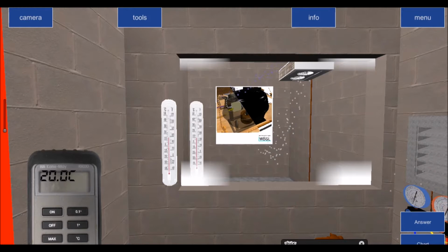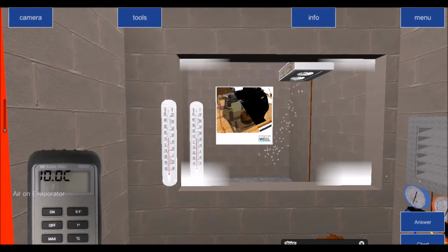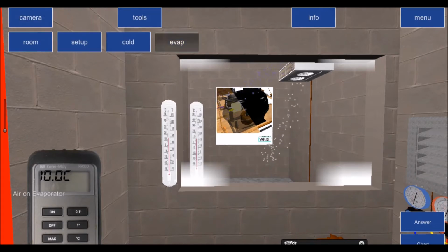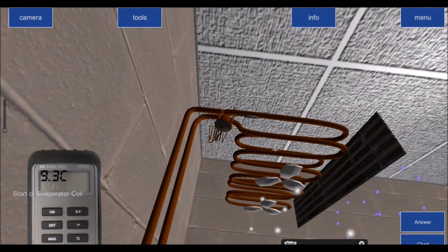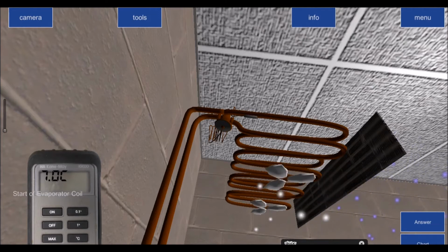Now, sticking with this particular job, we've got air coming onto our evaporator of 10 degrees, which matches up with our room temperature anyway. So what we need to do is determine what is the evaporating temperature and work out the delta T total. Evaporating temperature is 7 degrees. Now, is 7 degrees the normal temperature for air on of 10 degrees Celsius? No, because it's 3 degrees of a difference, isn't it? And it should be between 5 to 10 degrees of a difference, yeah?